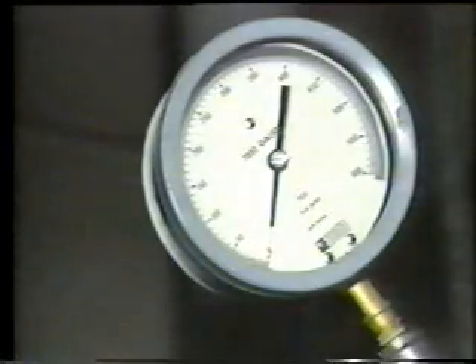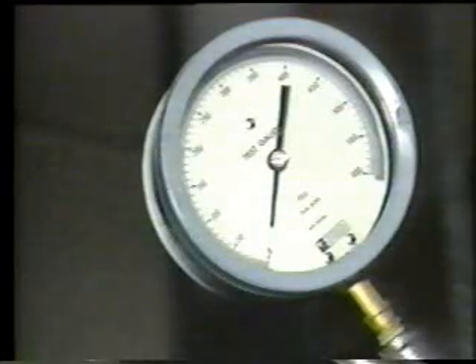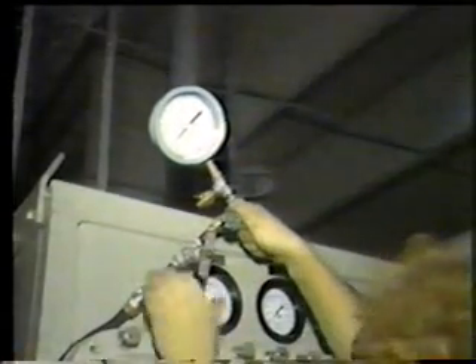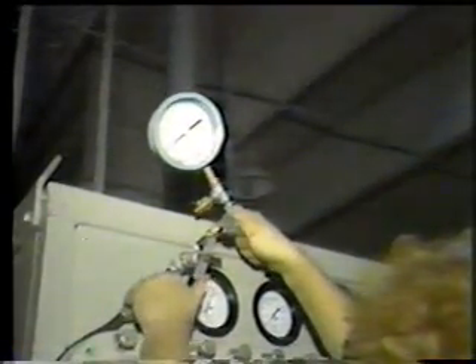Caution: in the next step, slow, even pressurization and depressurization is essential for accuracy and long life of the gauges. While holding the master test gauge assembly in position, slowly open the three-way hand valve to allow pressurization of both the master test gauge and the gauge to be calibrated. Increase supply pressure until the master test gauge stabilizes at the normal system operating pressure.